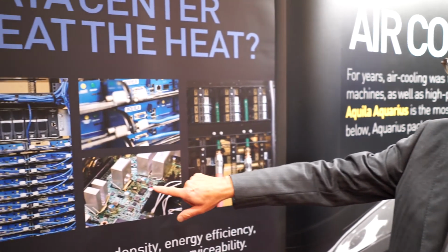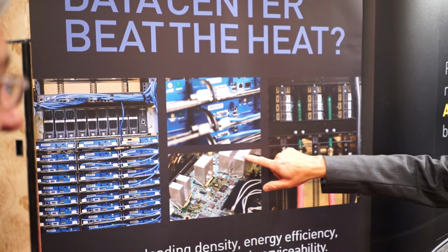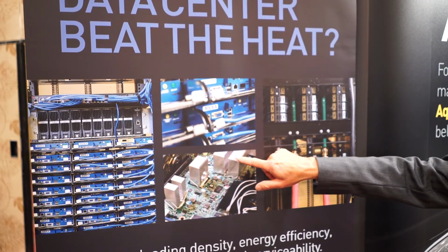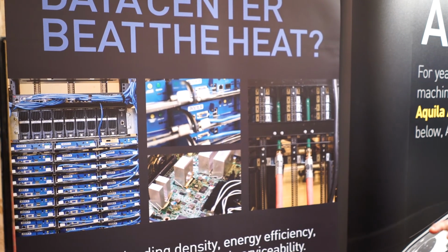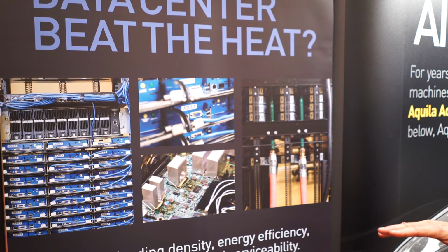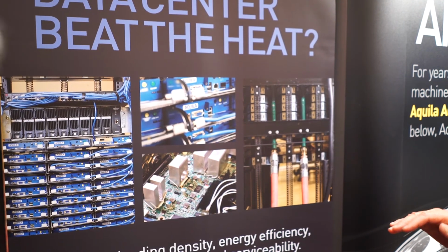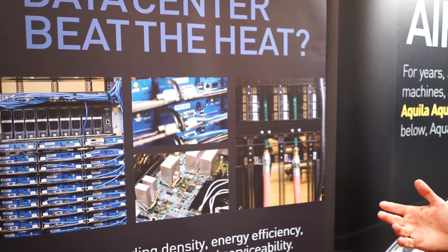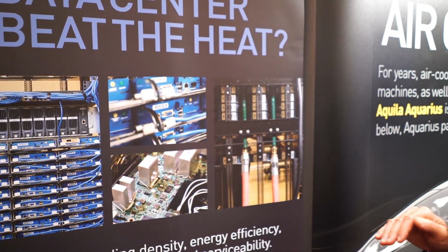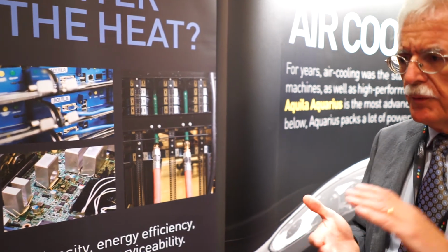How do you get the heat from the components to the plate? That's really pretty straightforward. Very simple, actually - you can see there's a chip under here. So we conduct the heat up to a single surface, which is generally the top of a DIMM. And then we put down a special layer of compliant thermal interface material, which we invented. So what it does is take up all the irregularities in the system, so you've got a very good connection to the cold plate.